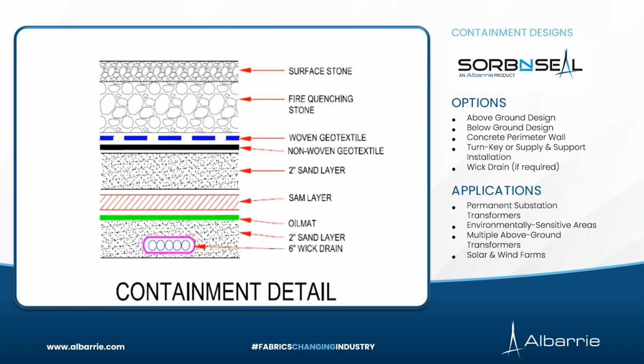And the purpose of that drain is to collect water passing through the layers of the system and direct it somewhere else. So you only need that drain if the soil is not naturally permeable. So for example, if the containment system or the substation is sitting on sandy soil, we don't need that drain because the water is going to naturally infiltrate and go into the soil below. But if, for example, the substation is sitting on an area where it's all clay, it doesn't really matter how much water the fabric can pass through, because once it hits the clay, it's not going to go anywhere and it's going to back up into the containment.